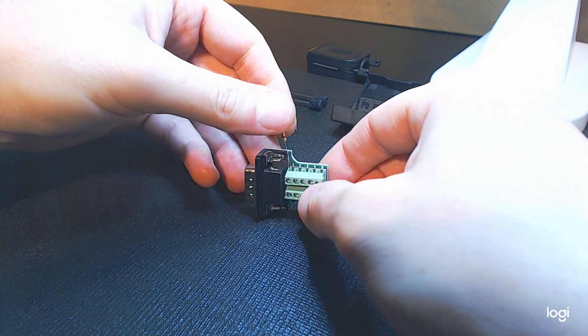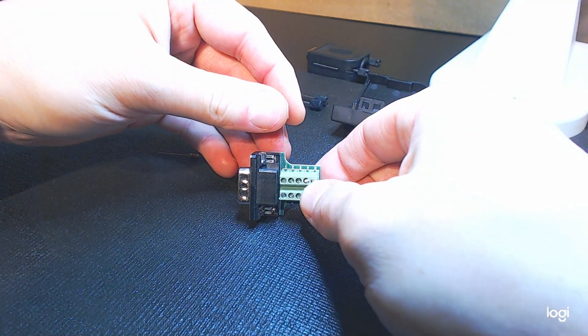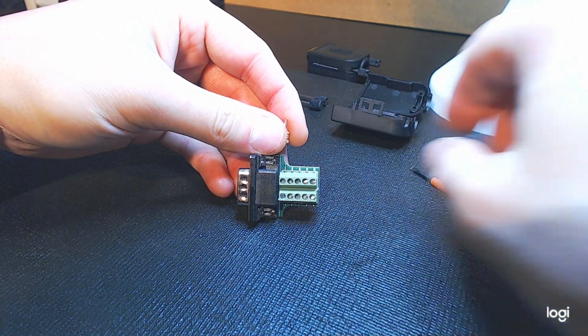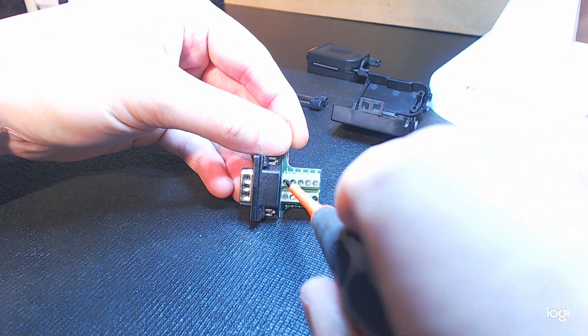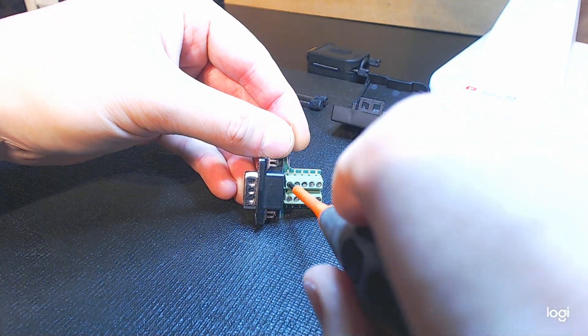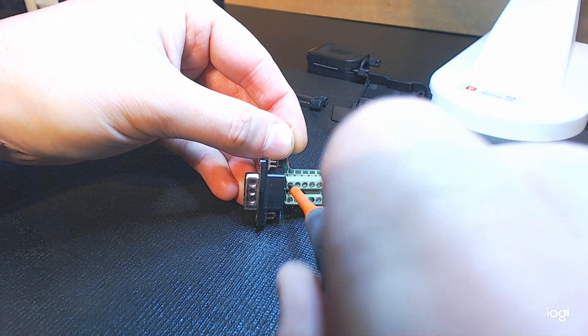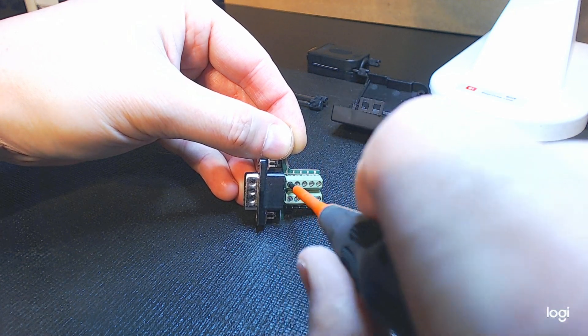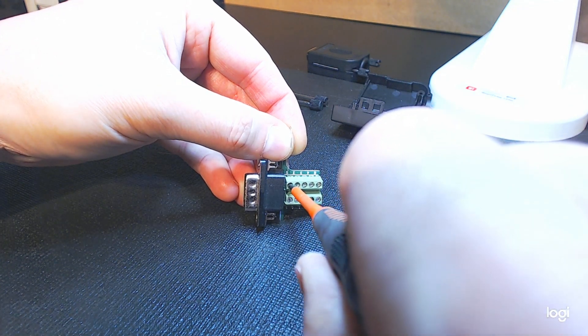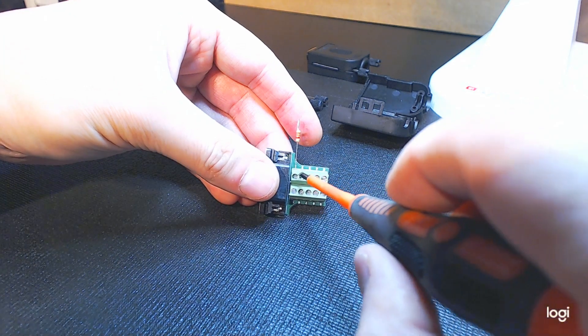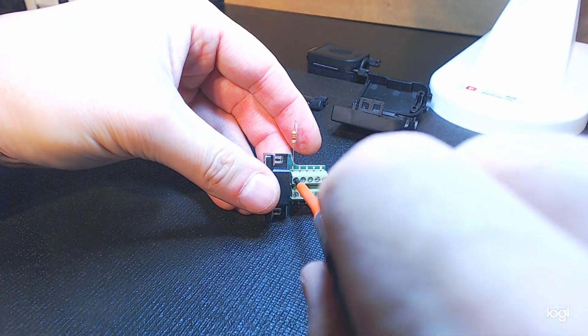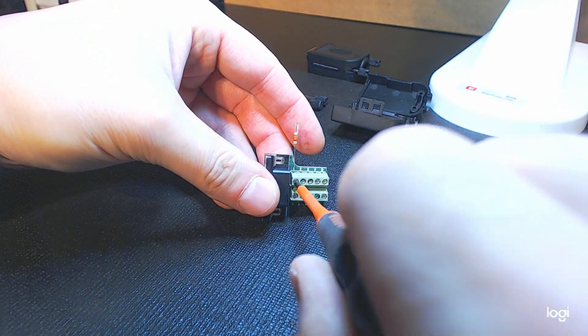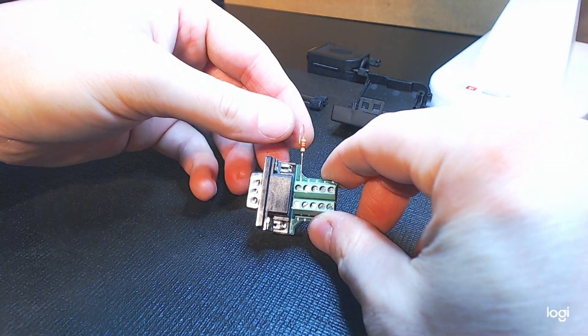So I'm going to go back in, and what I'm doing is taking the straight end of the resistor once again and going back into the terminal block one position that I was using before. I'm going to pivot my hand so you guys can see. Trying to keep the resistor nice and symmetrically straight. Tighten it slightly. And when I say slightly, just a little bit of pressure, once it bottoms out, we're only looking for about 10 ounce inches of pressure, which is very little.